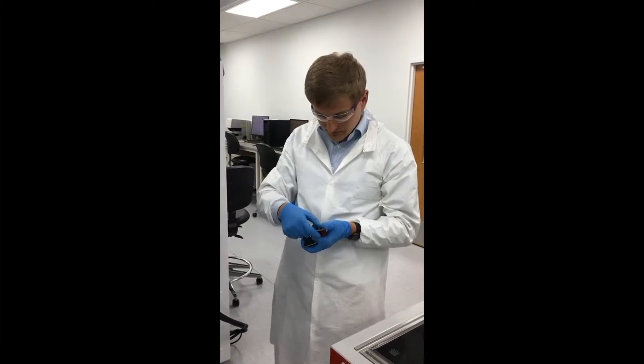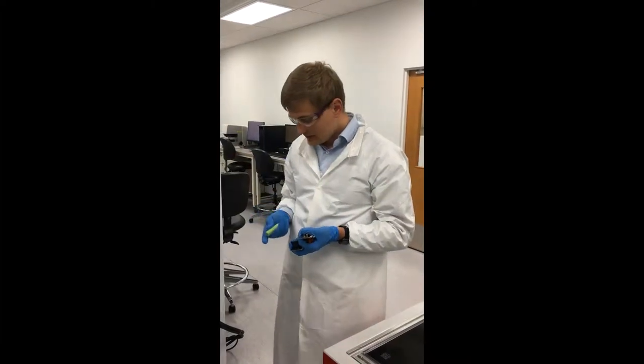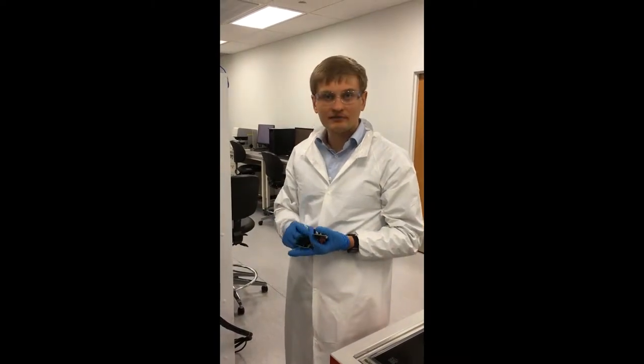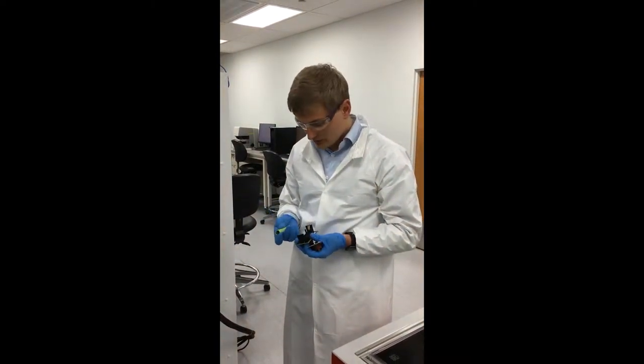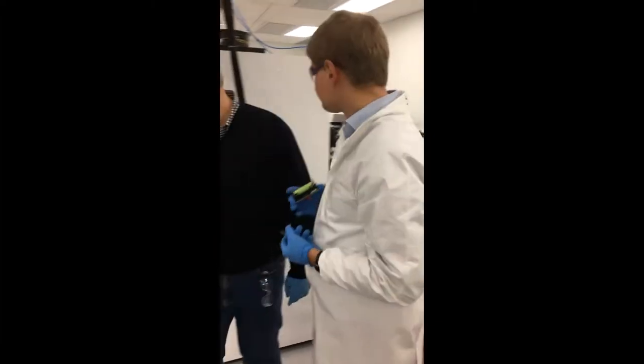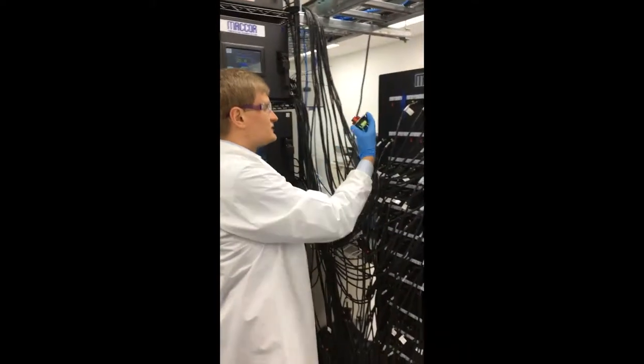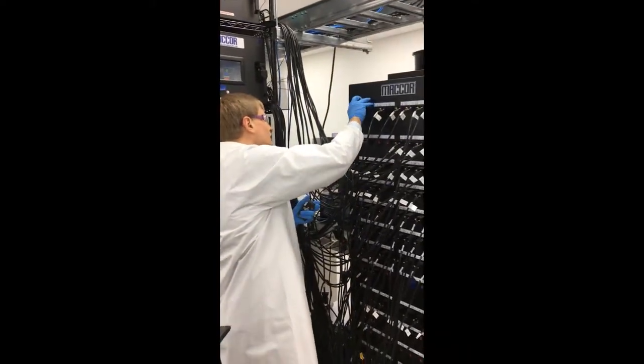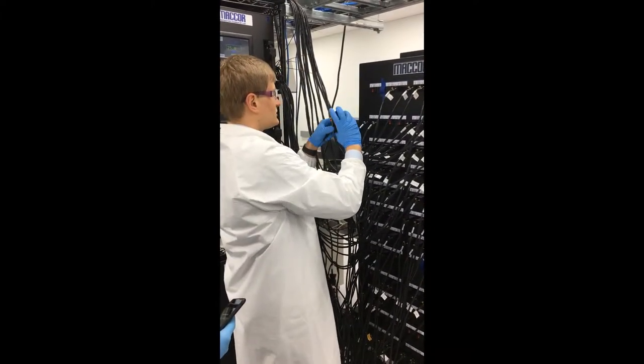We have this device here called Maccor. It has 100 channels. We can connect two batteries for our demo and just show how we can charge and discharge them. So I'll just plug them in here. We have four. These are channels. We'll just use the first two channels for the day. And we will connect these things.